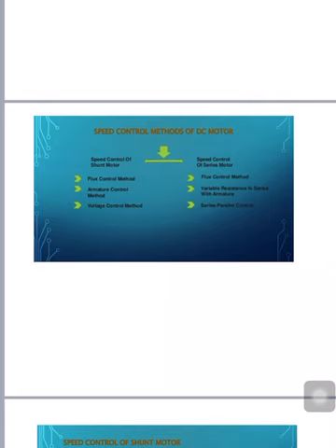Whereas in field control, the adjustment can be obtained by means of a small rheostat, and relatively good speed regulation is obtained for all speeds. But with armature control, a bulky resistance is required. So if we use both methods simultaneously, the cost of the machine will increase a little bit. We will get a large range of speed control, and to neutralize the effect of power loss, a heat sink can be used. This is how DC shunt motor speed control is achieved.